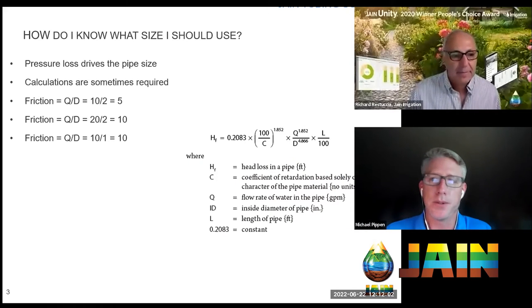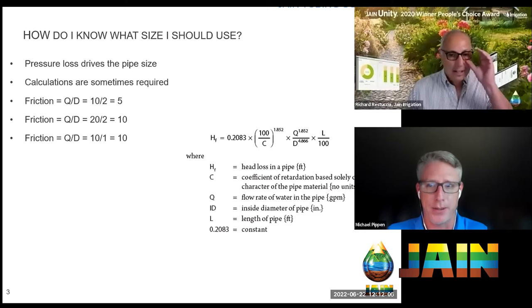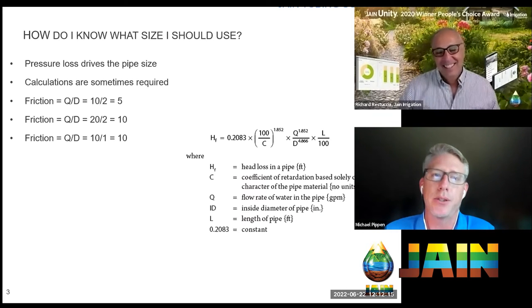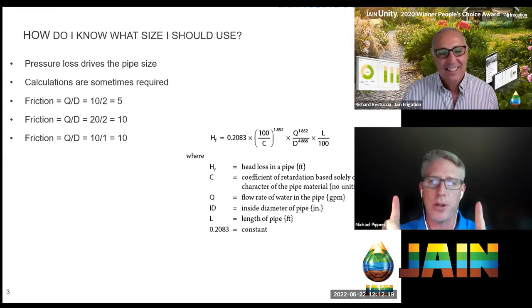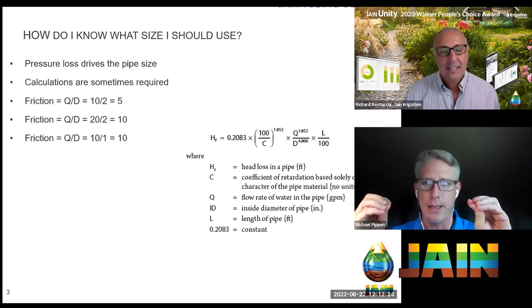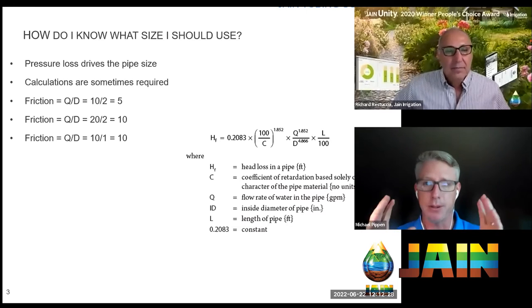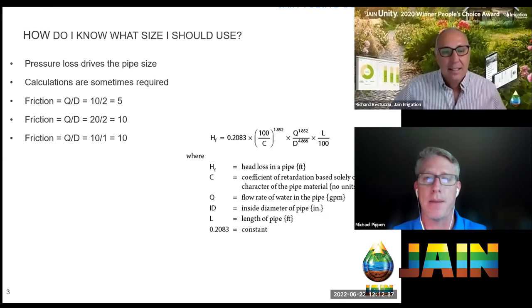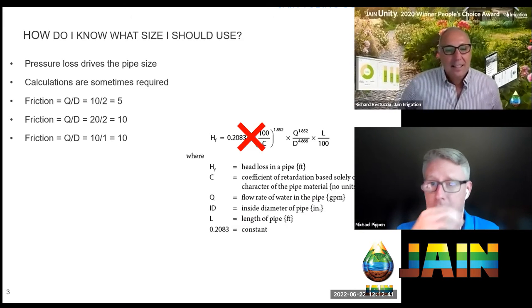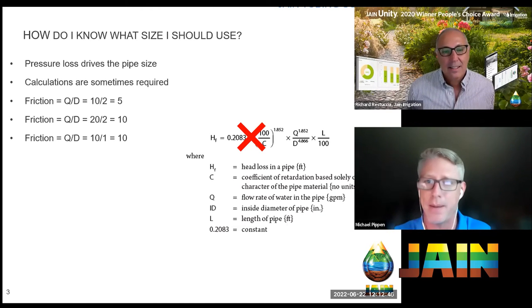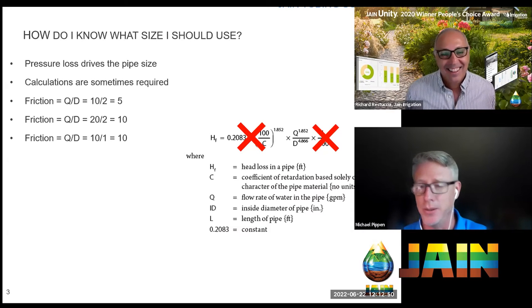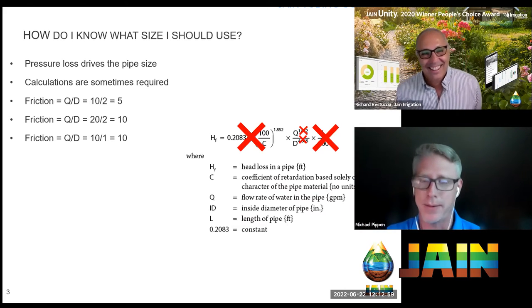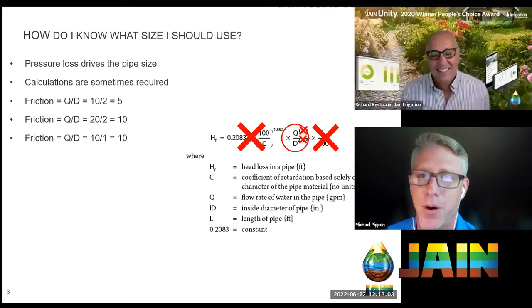And then also, where are they located on that pipeline? Are they all at the very end, 1,000 feet away? Are they spaced evenly across that pipeline? In these initial discussions, I want us to just think about an inlet pressure of 40, a required pressure of 30, one singular device at a certain distance away. That's kind of where we're going to start this conversation. I think that's the basic information you need to start designing a pipeline. So I have a couple of questions. In landscape, I've never seen a situation where we couldn't get at least 40 PSI. We always had to reduce. But I think in ag, quite potentially, there's times when you don't even have 30 PSI. That's absolutely correct. And that's not necessarily a good thing. Sometimes we're adding booster pumps. This target pressure could be below the system pressure that's given.